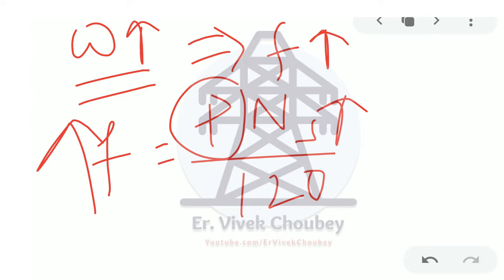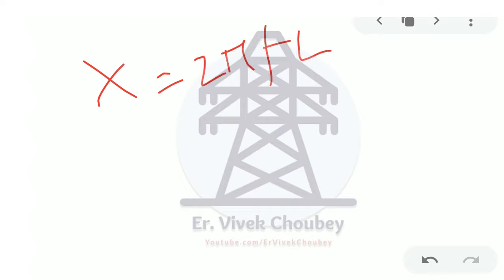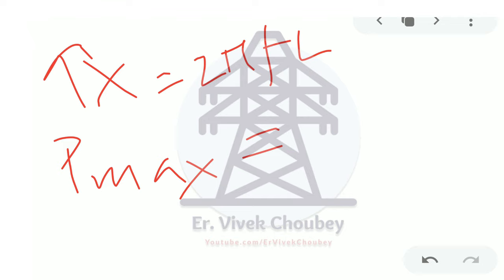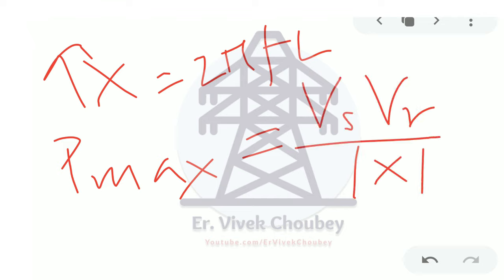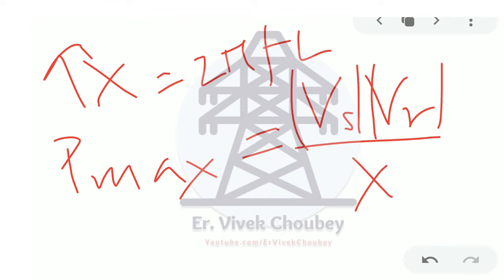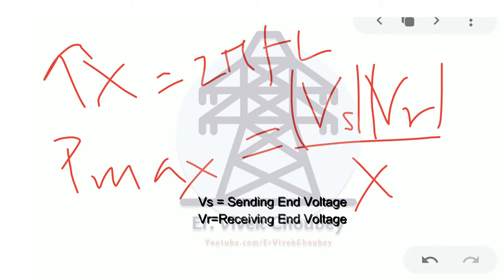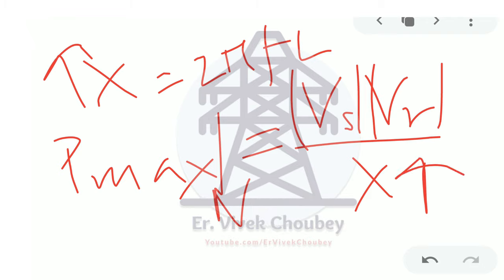Now what happens with an increase in frequency? There will be an increase in the line reactance. X is given by 2πfL. So if f increases, obviously X will increase. Why is that problematic? Because the maximum power sending capability in a transmission line is given by VS VR upon X. So Pmax is VS VR upon X. Now if X increases, that means there will be a reduction in the entire Pmax, that is, the maximum power sending capability.